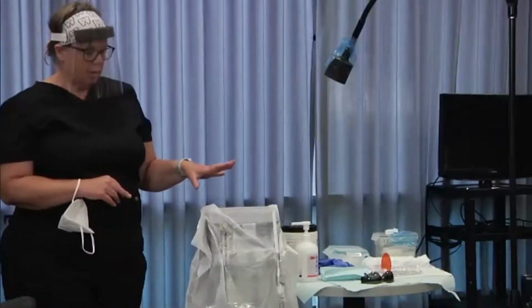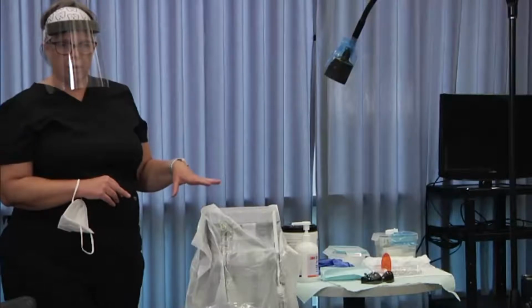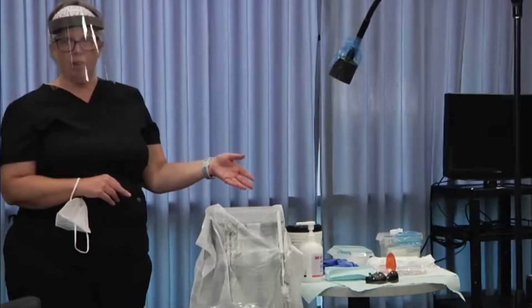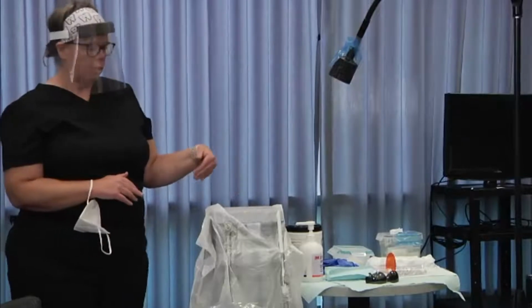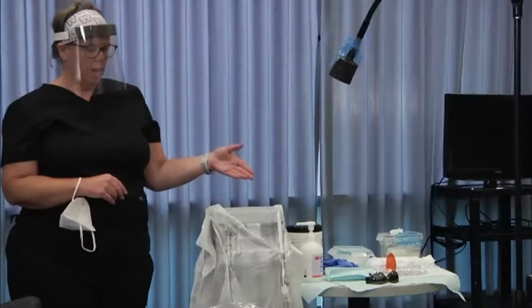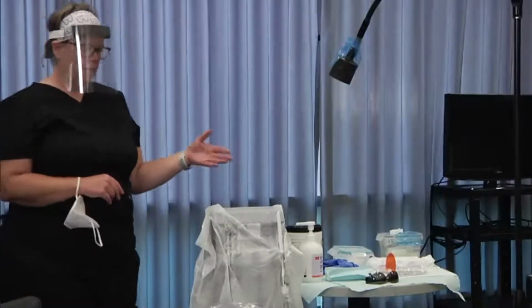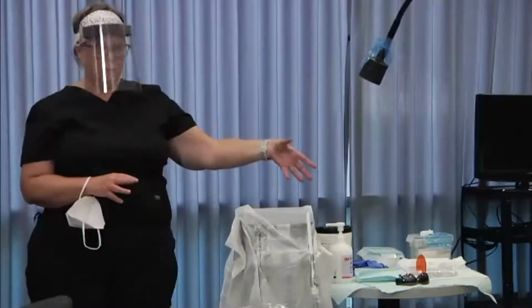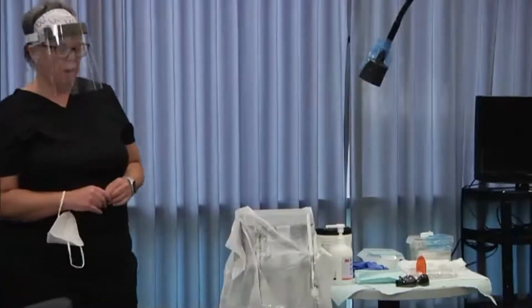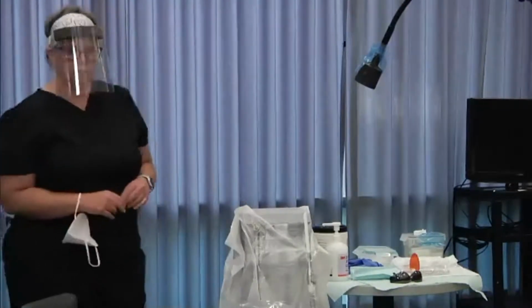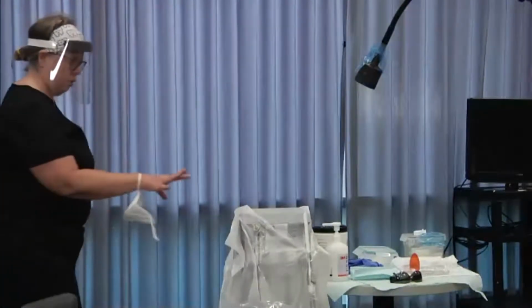A note about the suction, if you're doing aerosol generating procedures, it's required that you use high evacuation suction. Dental work compressors, you can't have a saliva ejector and high speed and high evacuation suction on the same unit. So you would have to have a separate unit that would offer the high evacuation suction, and then you could have your saliva ejector on this unit.